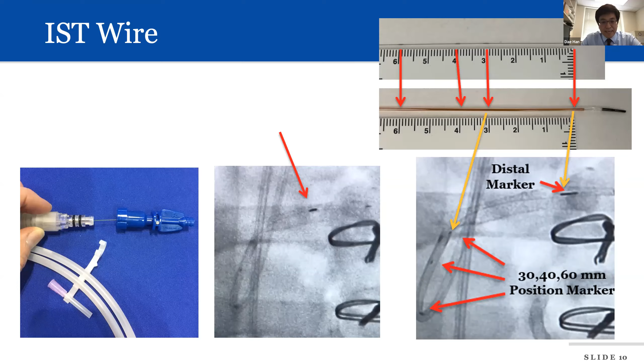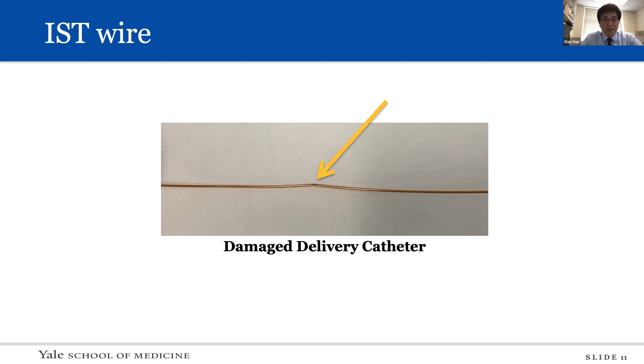Once we place a catheter, the radiation oncologists move the IST wire back and forward to check for any damage to the catheter. When they move the IST wire, they will feel something in their hand. Once the radiation oncologist is done with the damage test, they will fully retract the IST wire and then engage the delivery catheter to the transfer device. And this is an example of a damaged delivery catheter. We found this damage during the IST wire test, and then we replaced the delivery catheter to complete the treatment.